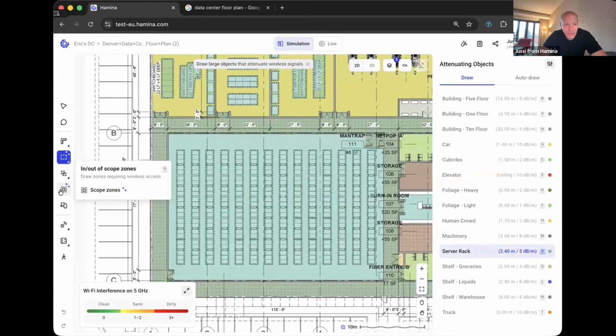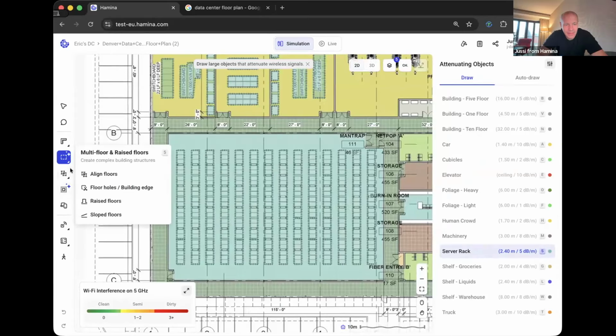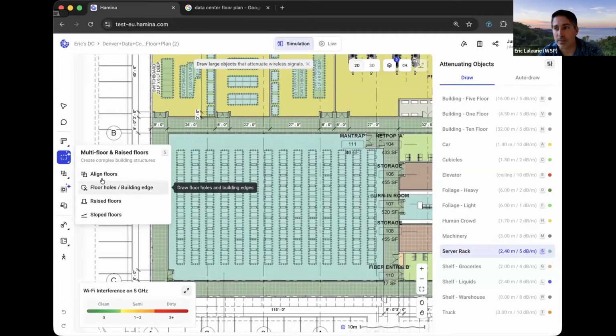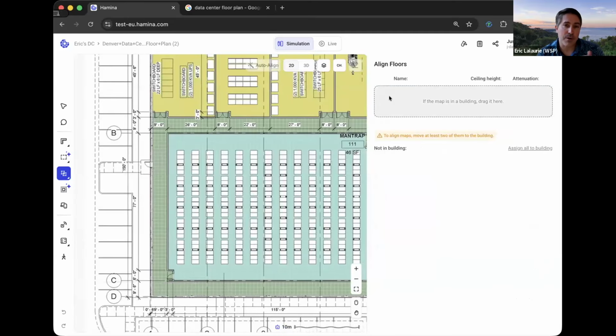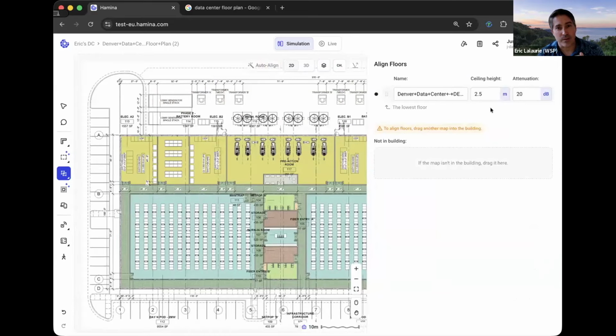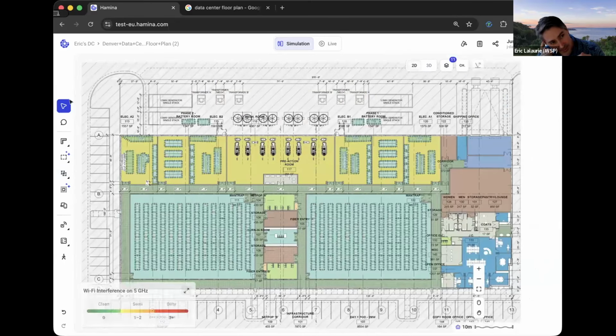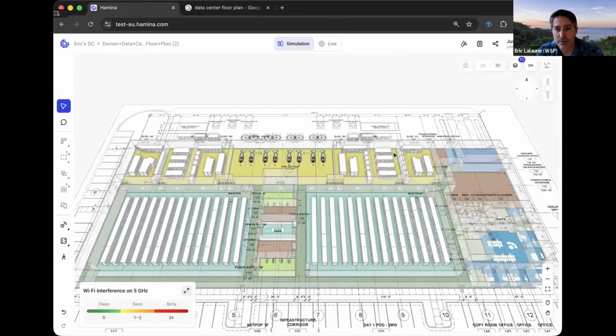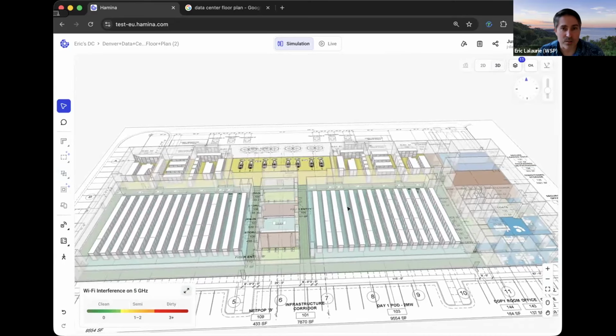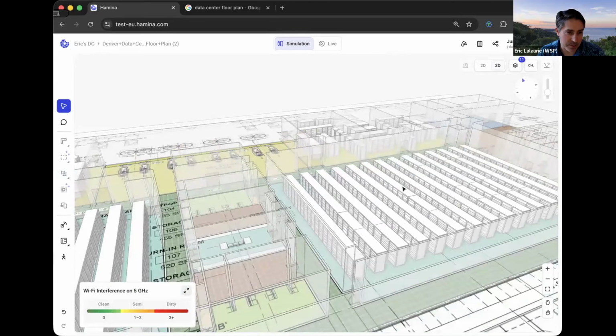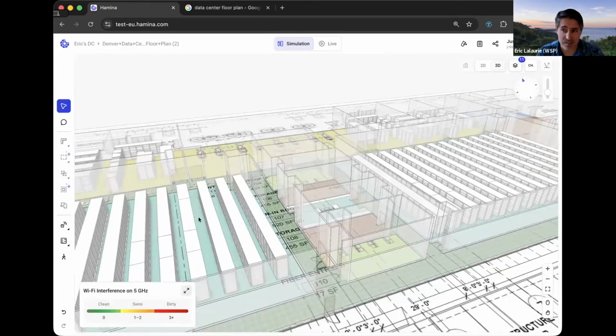What about the height of the building - what would you typically have? You'd have to have slab about 5 to 6 meters. It depends, because you have to imagine you have the racks, and then you have to run all the infrastructure - telecom, electrical - in between the rack and the ceiling. Usually you'll have a ceiling. I might expand on that later - I've got a couple of pictures set aside, all public, so I can show you a little bit how it's built in practice, especially in the hyperscale environment.